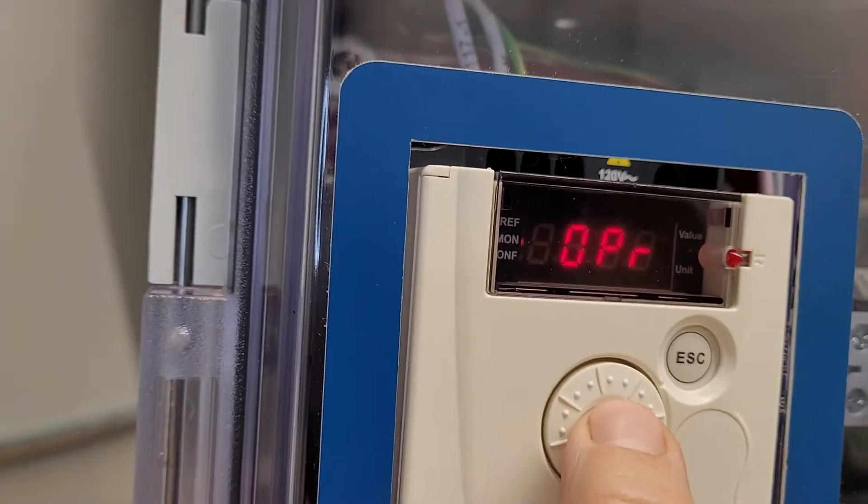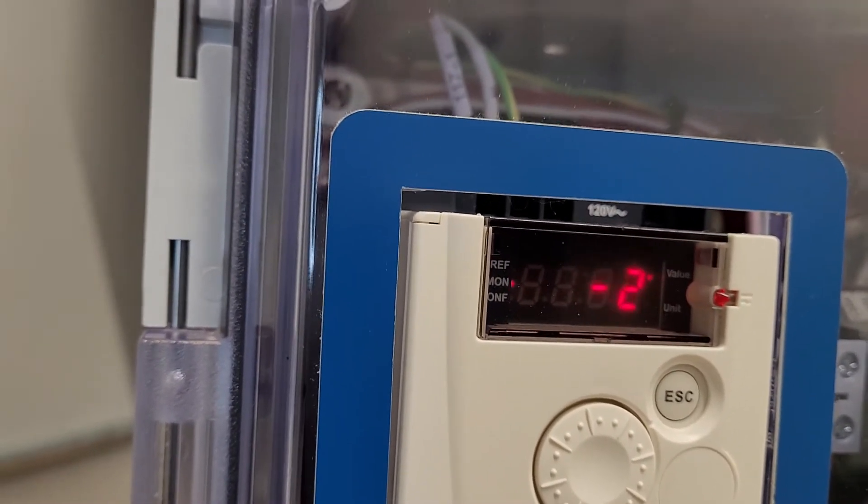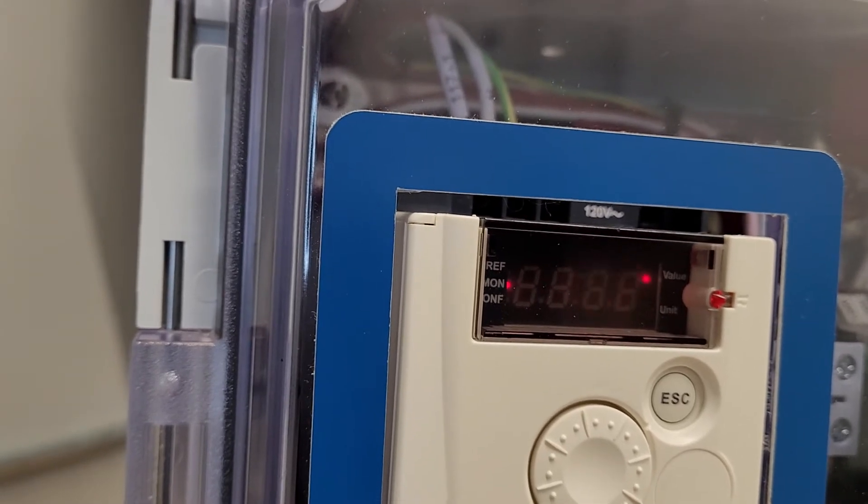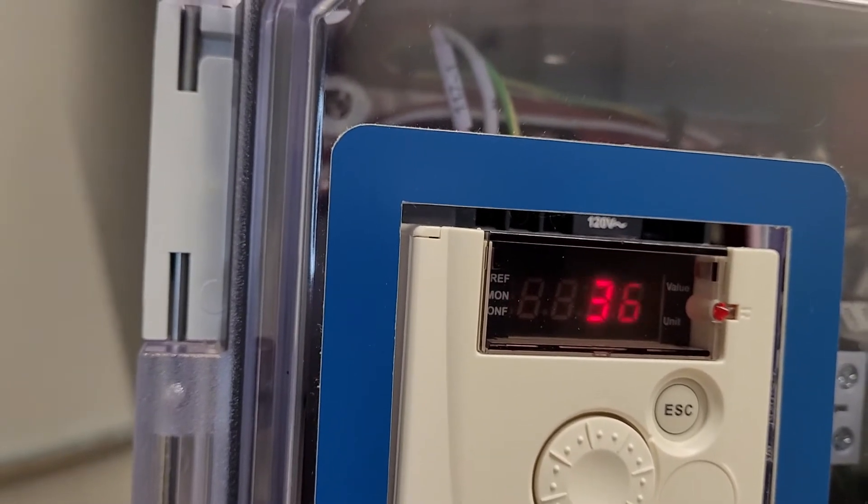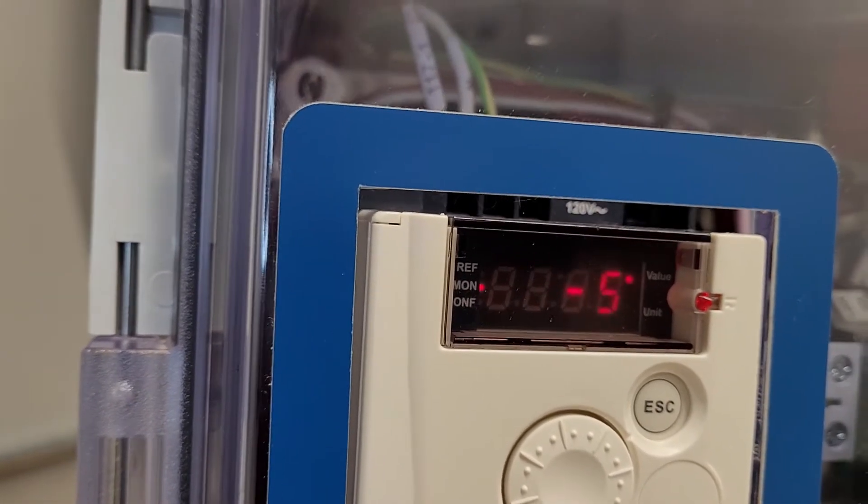The output power of the motor is around 23%. Now watch this. I will do a quick deceleration. You will see it go negative because if I slow it down really quickly, it regens back to the drive. That is why it is showing a negative value.